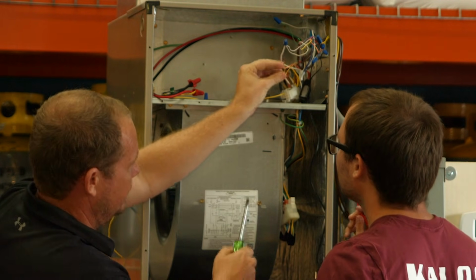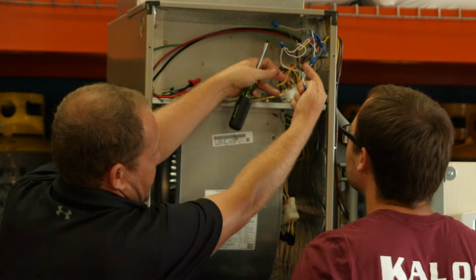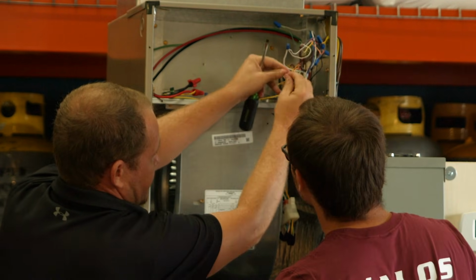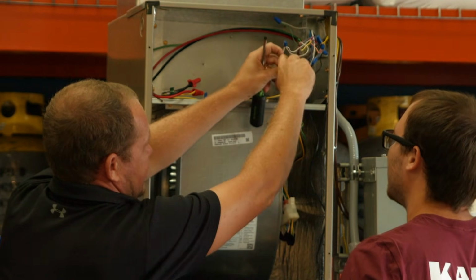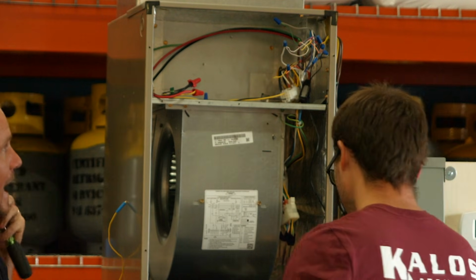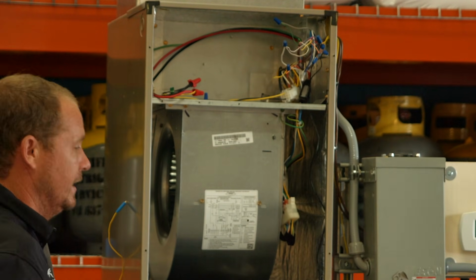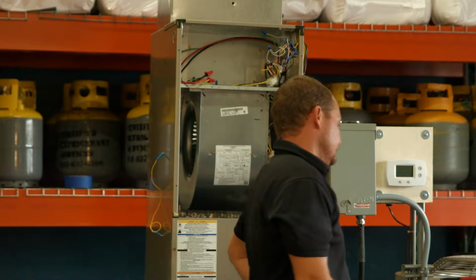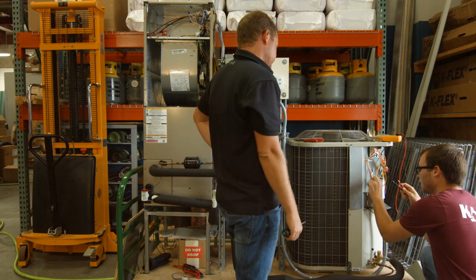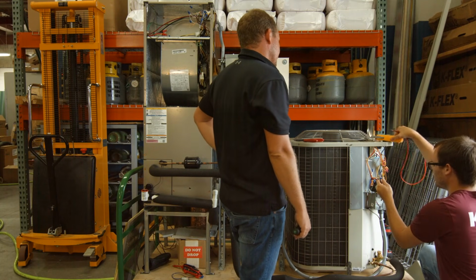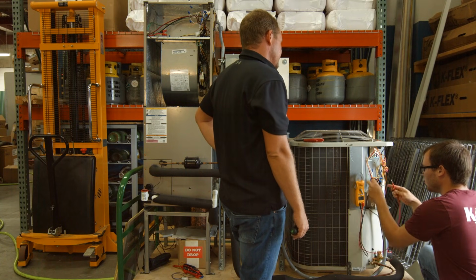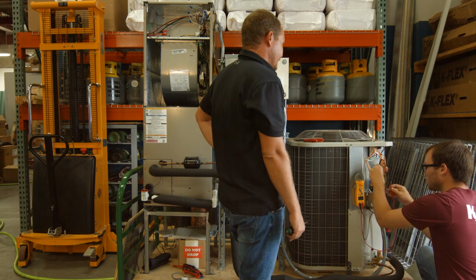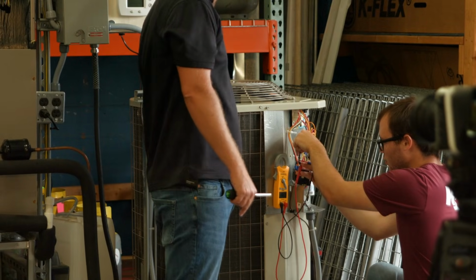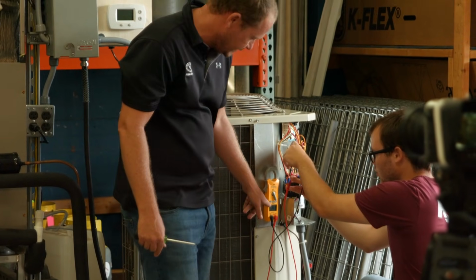And then outside, because these are in the same conductor going to the outside, we're going to connect these together, and then go outside and check in between orange and yellow and see if you have a path. Do I need to wire them out on this, or can I just take it? In this case, because we already know it's an open, we can just do it that way. Normally you'd isolate them to be sure, as long as you know those are pushed in really well and making good contact.